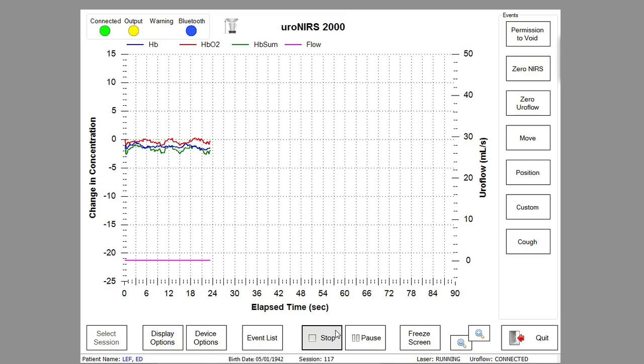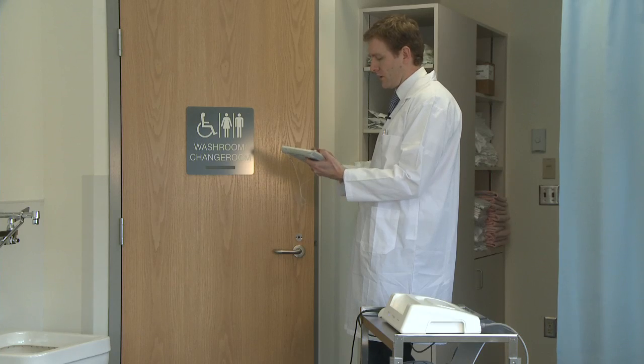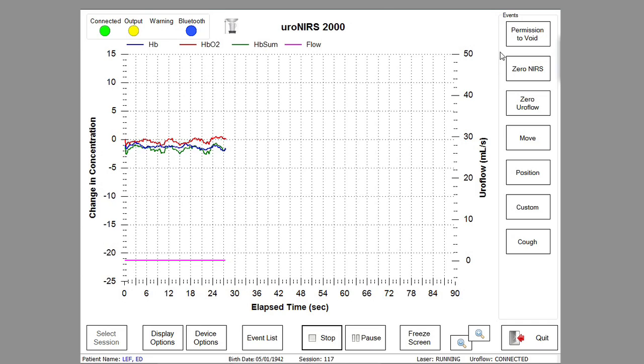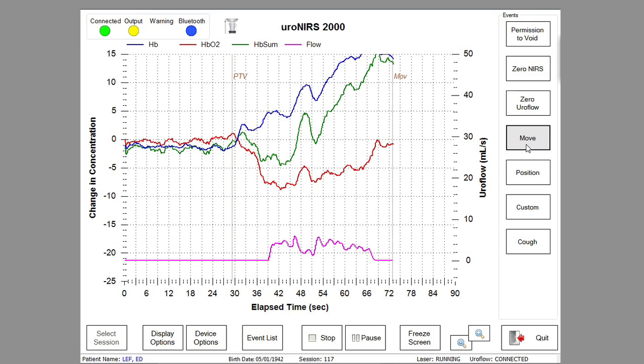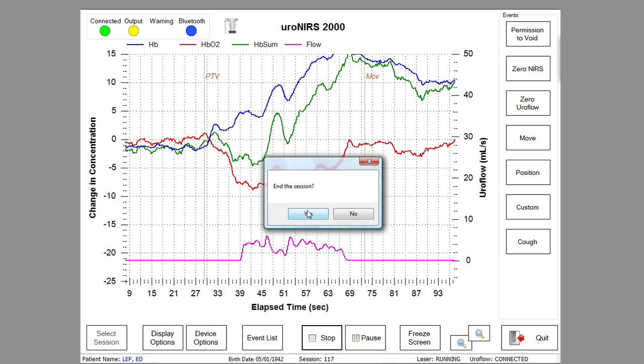Once a baseline has been established, you may instruct the patient to begin voiding and at the same time tap the Permission to Void event marker. As soon as urine flow is detected, the changes to uroflow data will be displayed in real time. During the test, you can annotate events by clicking on the predefined event buttons or add comments with the custom event button. When urination stops, click the Stop button to end the session and save the data.